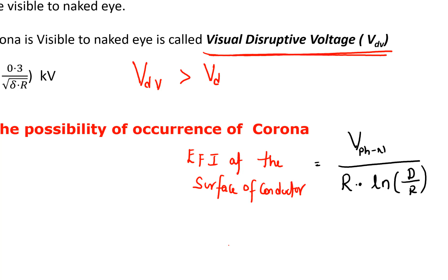Now you can see, as we increase the transmission voltage, then obviously the phase to neutral voltage of the conductor increases and the electric field intensity at the surface of the conductor also increases. So for this reason, we cannot reduce the voltage of transmission. So to reduce the electric field intensity, what is the other option we are having? What we can basically do is we can increase the size of the conductor. So that is the fundamental idea in avoiding corona or reducing the effect of corona. Okay.